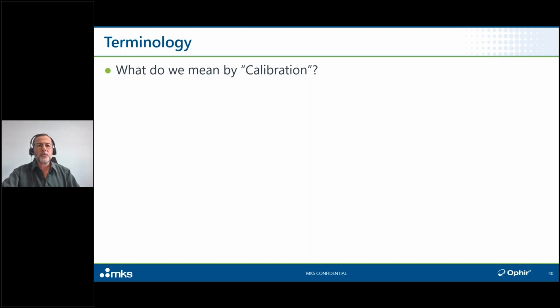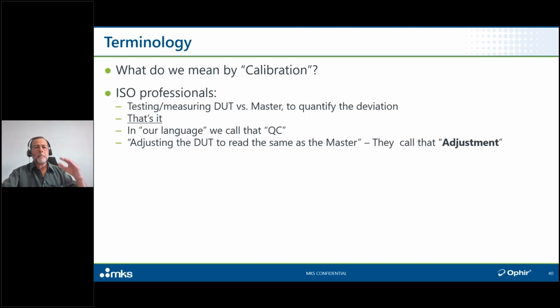The quality assurance professionals, when they use the word calibration, they mean specifically measuring the deviation and stopping there, not adjusting the instrument so that it then reads the same as the reference. They have a different word for that. They call it adjustment. So it's just important to know how to translate from QA language to engineering language.